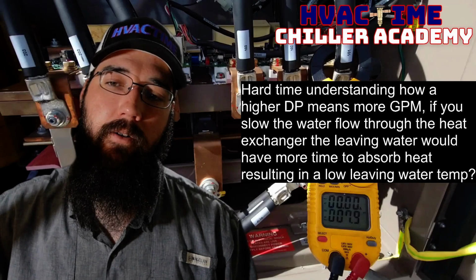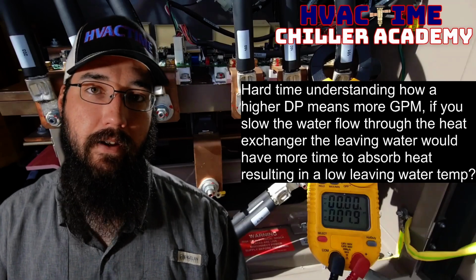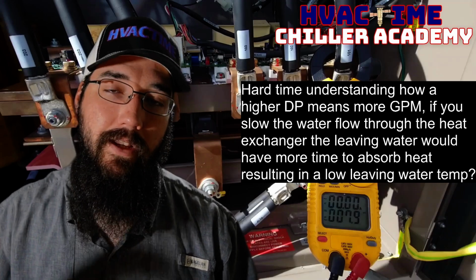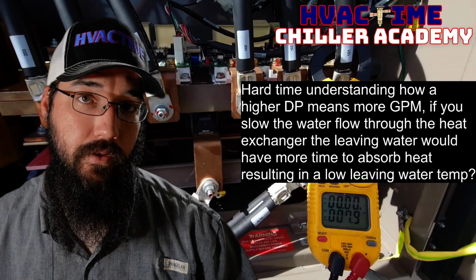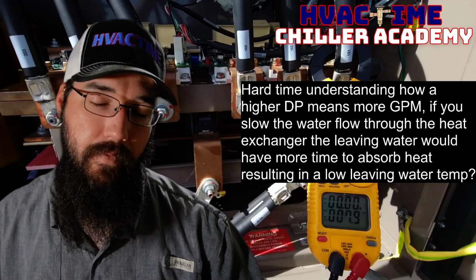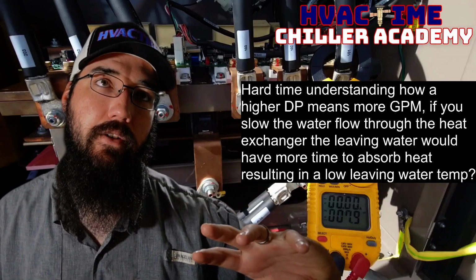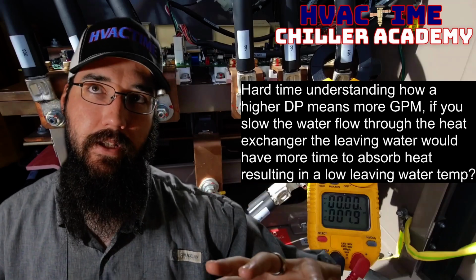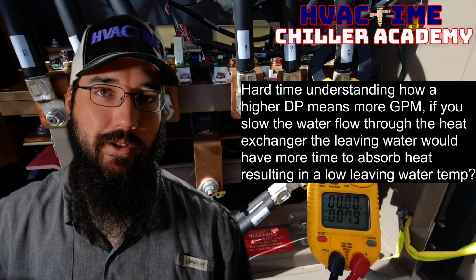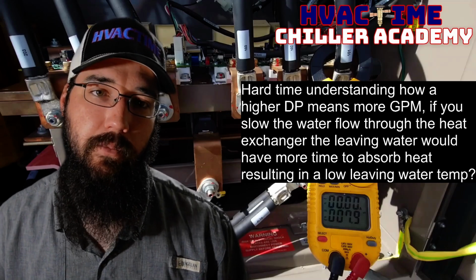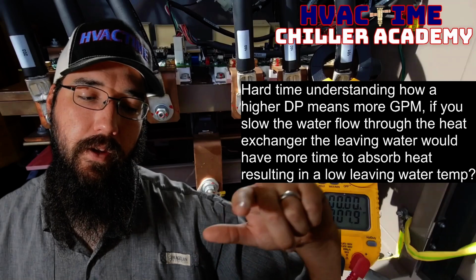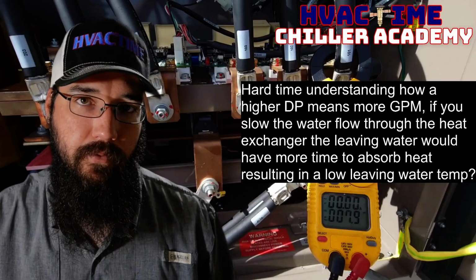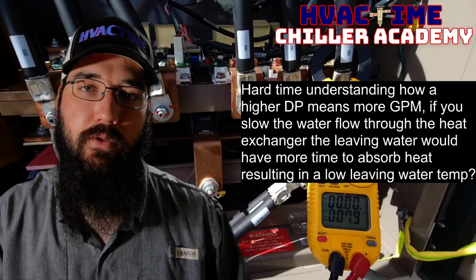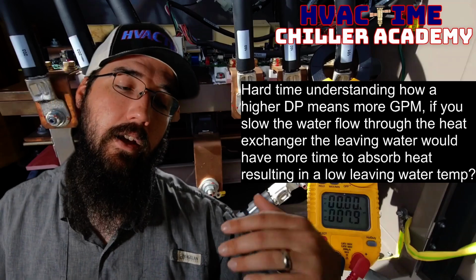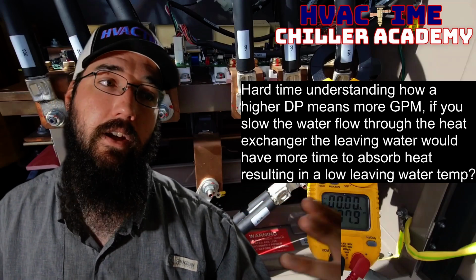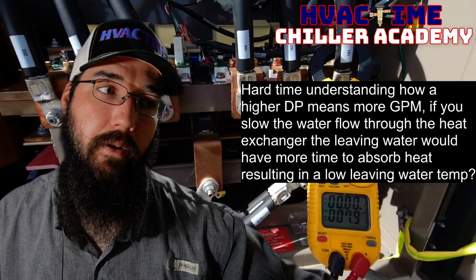When we are running a low GPM, something we have to be mindful of is we could have a really good temperature difference, or TD, across our heat exchanger. But because we don't have enough GPM, we're not actually moving that much heat. So our chiller is not staging up that much. What that will also mean, though, is that the whole space, whatever we're cooling, if it's comfort cooling, the building space will begin to get uncomfortable for the tenants. If it is a manufacturing process, we're going to struggle keeping up with the manufacturing equipment.